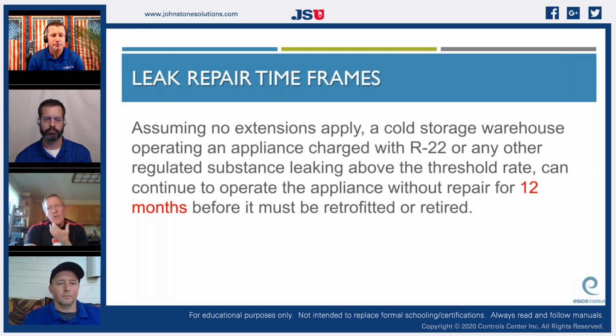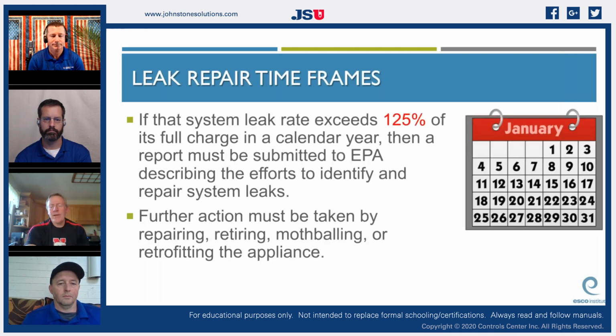Assuming no extensions apply, a cold storage warehouse operating an appliance charged with R22 or any other regulated substance leaking above the threshold rate can continue to operate the appliance without repair for 12 months. And this one always blows me away. I was talking to Brian about this yesterday. If a system's leak rate exceeds 125% of its full charge in a calendar year, you must submit a report to the EPA. That's a lot of leaking right there, guys.